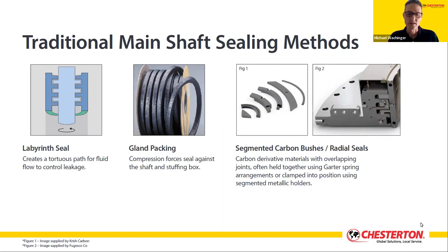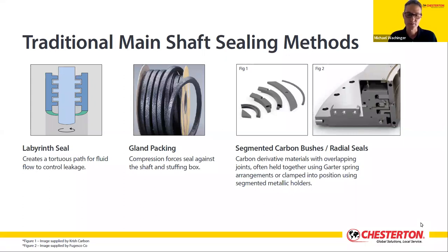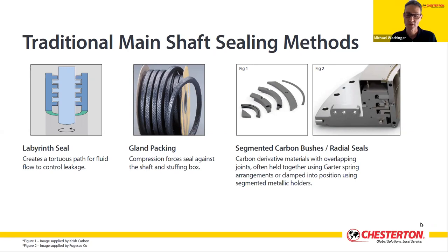One advantage that gland or mechanical packing has is that it tends to support the shaft it is sealing against, so axial or run-out movements can somewhat be tolerated. Then came along segmented bushings or plates — originally made using metal-to-metal surfaces, a softer metal such as bronze against a harder metal such as stainless steel, with lots of cooling or flushing liquid required. Eventually the softer material was replaced by carbons or derivatives of carbons, and these segments were introduced to greatly reduce friction and therefore the amount of flushing water required.